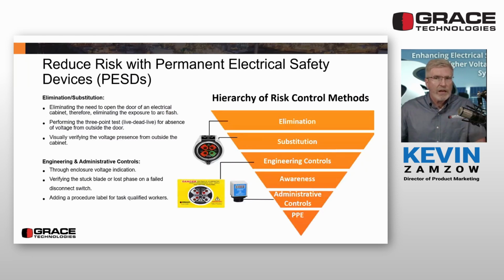Risk reduction is key to creating an electrically safe work condition. Use the risk control hierarchy principles of elimination, substitution, engineering controls and awareness, administrative controls, and personal protective equipment to reduce risk to an acceptable level. Grace Technology safe test points and CheckVolt eliminate the need to open a panel to perform absence of voltage testing, an example of elimination. Our voltage indicators are used to increase awareness of the presence of voltage, for example, from residual capacitance.